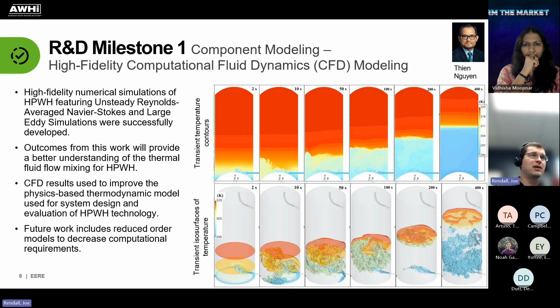We went in pretty deep on that, and I'll also talk about the heat exchangers later. The system model included centralized drain source heat pump water heater configurations. We looked at 6 or 7 of them, and only one turned out to be cost effective compared to the others. We also modeled central air source heat pump water heaters, and used engineering calcs approximating unitary air source heat pump water heaters pulled from references and compared to experimental data.